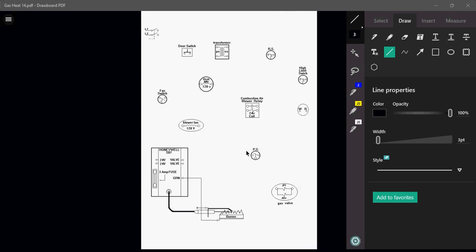Because now we have to think about it. We are in gas. It's a gas furnace. Gas is a combustible material. If it's not properly set up or not working properly, it can create an explosion. It can damage the furnace. It can even level a house if it's not working right. So the safeties on a lot of our furnaces are vitally important to make sure that they are wired correctly, the way they're supposed to be in the system, and we have to make sure that they are working correctly when we are working and maintaining and doing work on any sort of gas-fired equipment, whether that's natural gas or propane. Okay, so with that being said, let's talk about how this actually gets wired.